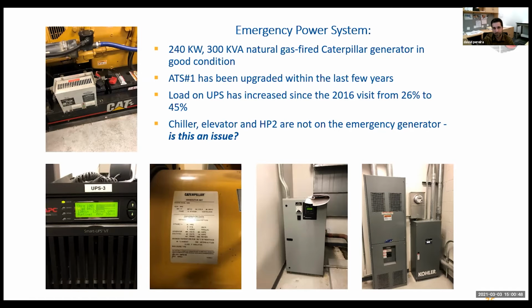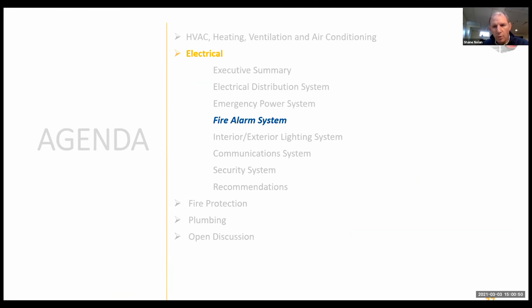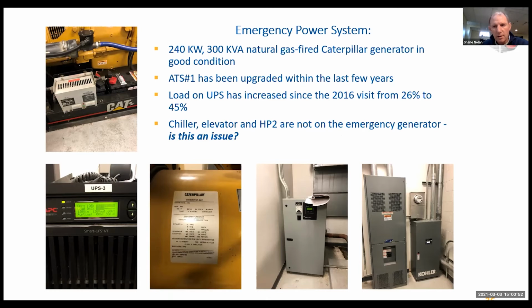Is the elevator required to be on emergency power? No, it's not. A lot of times in public safety buildings, the whole building's on emergency. There are reasons for not putting a chiller and elevator on emergency power, since those are the biggest loads in the building.